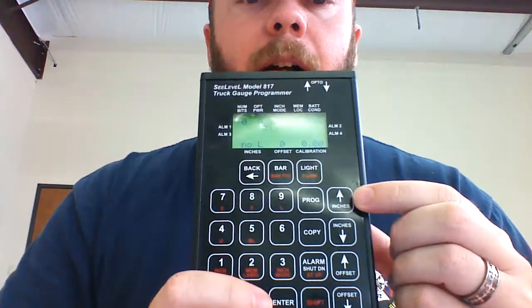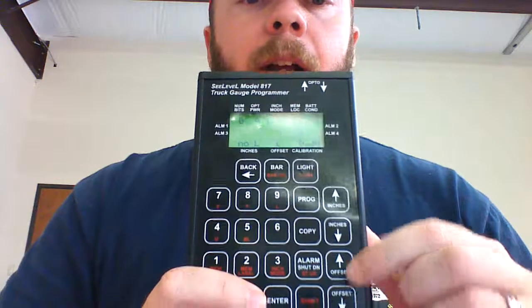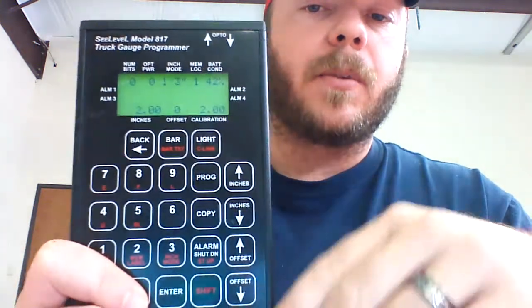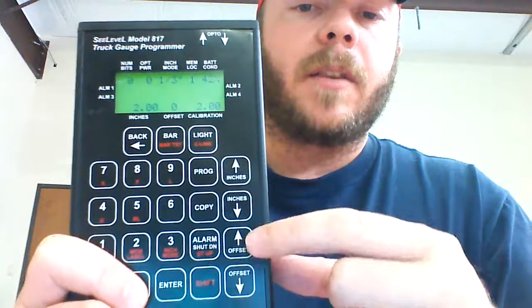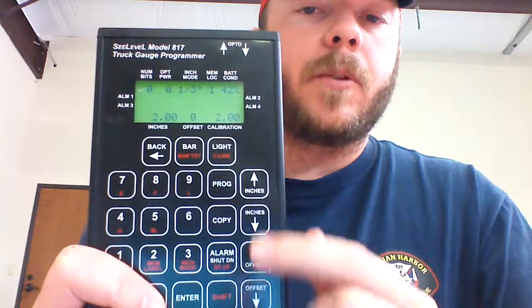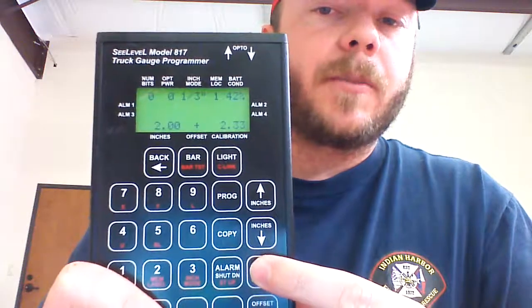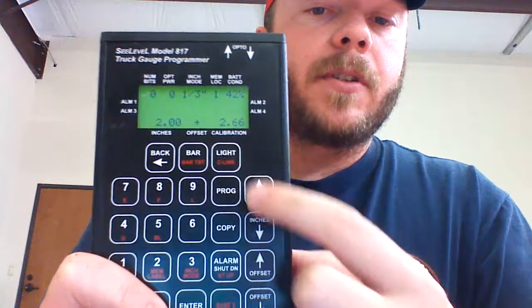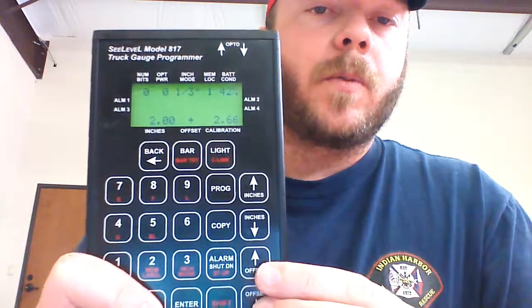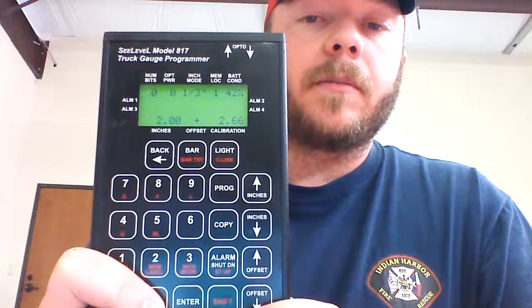Over here we have the inch arrows and the offset arrows. The inch arrows are what we're going to use most of the time, and as you can see, if I select the inch arrow up, both the inch value and the calibration move. What this indicates is it's simulating the float moving up and down on the bar. The offset arrows are how we adjust our offset. We're going to change the link between an inch value and the calibration. If I can demonstrate that there, you'll see that the calibration side moves, but the inch value stays the same. So when we set an offset to make the display read out an accurate barrel or gallon value, these are the arrows that we use there.